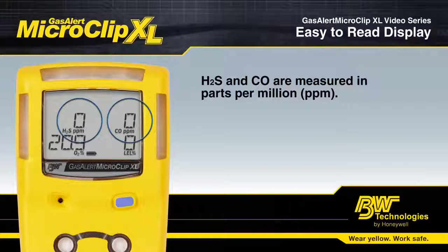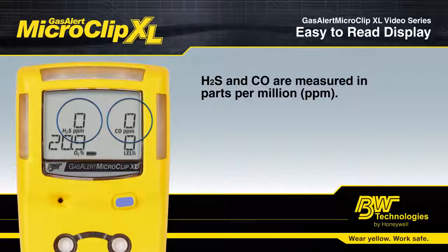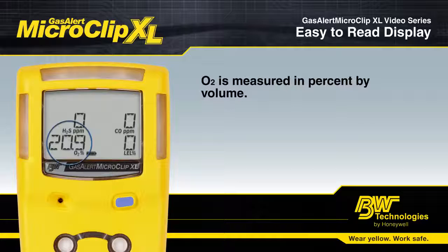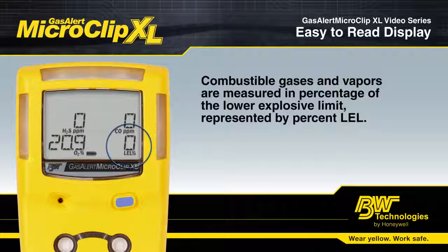When your detector is in standard operation, you will see the concentration readings displayed simultaneously. Hydrogen sulfide and carbon monoxide are measured in parts per million. Oxygen is measured in percent by volume. Combustible gases and vapors are measured in percentage of the lower explosive limit, represented by percent LEL.